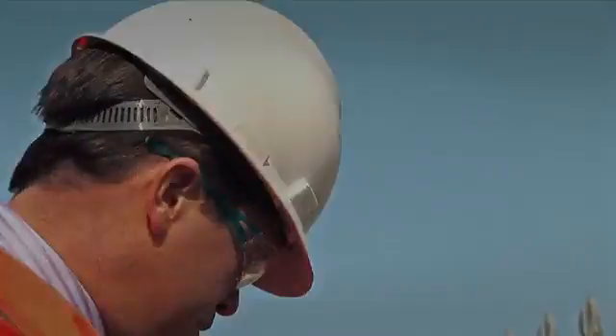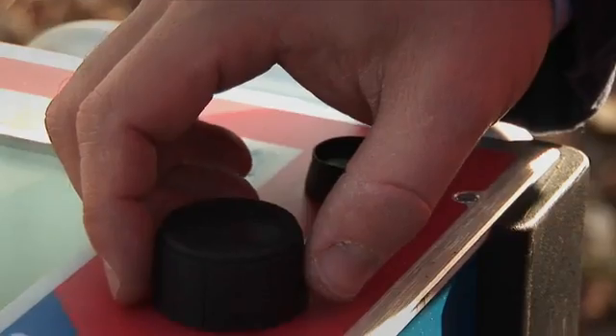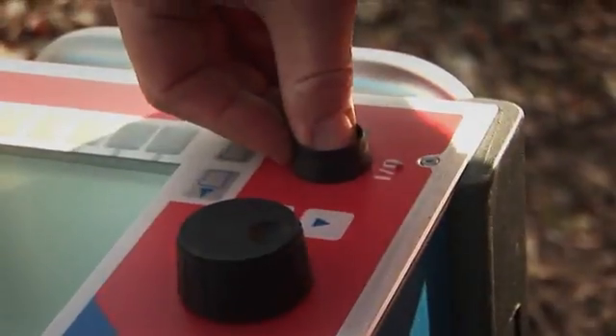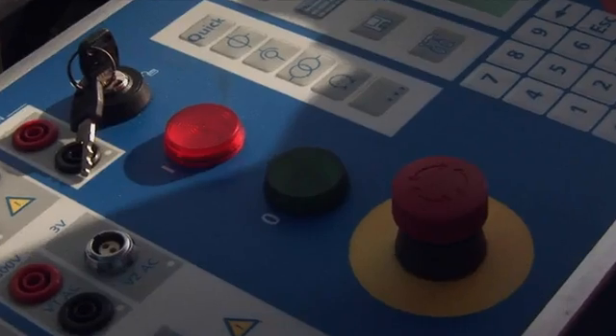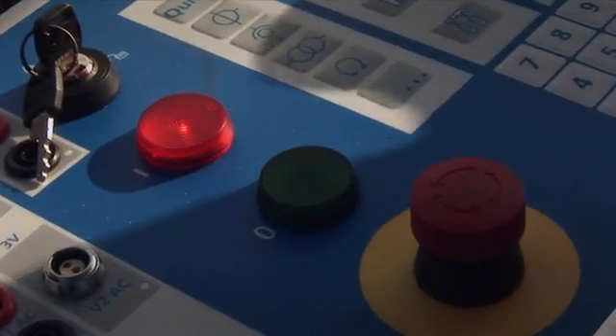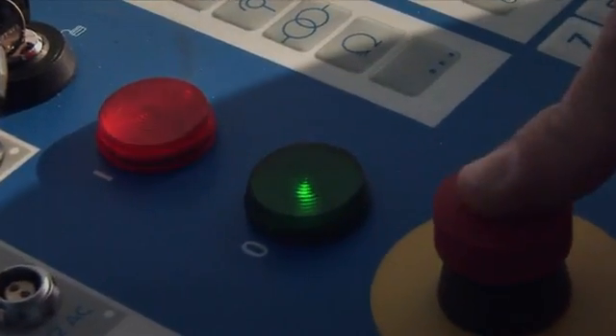Other tests as well include using the advanced test equipment, the CPC 100 and tan delta test set, to look at tap changer continuity, winding resistance, tan delta, and the tan delta of the bushings, giving you a clear picture of the insulation materials as well.